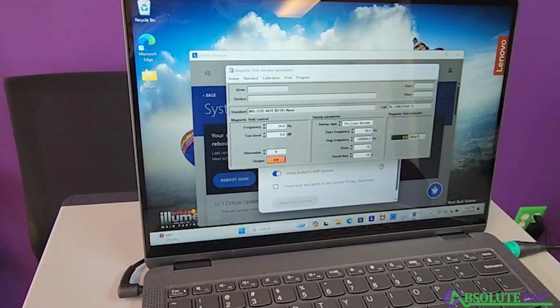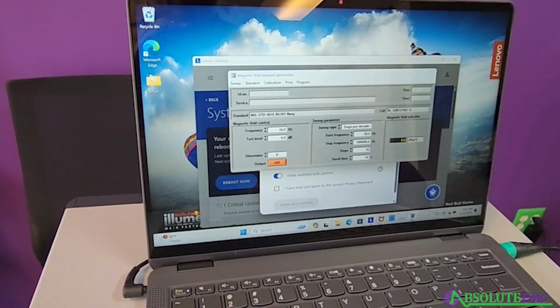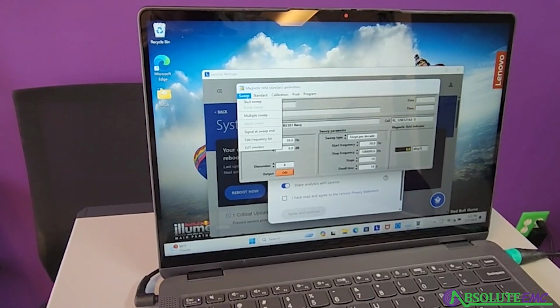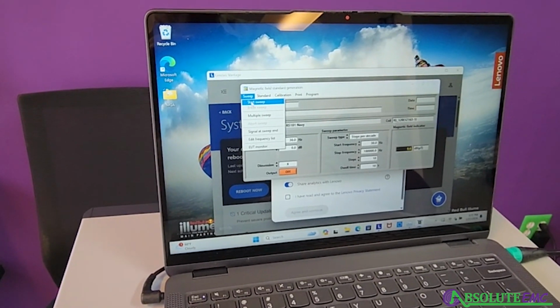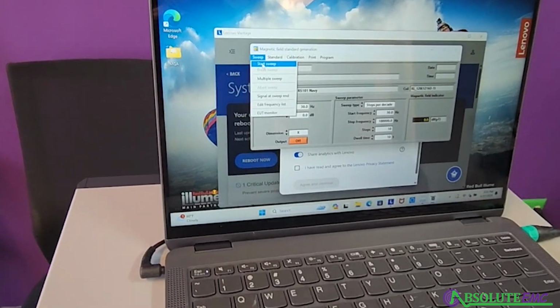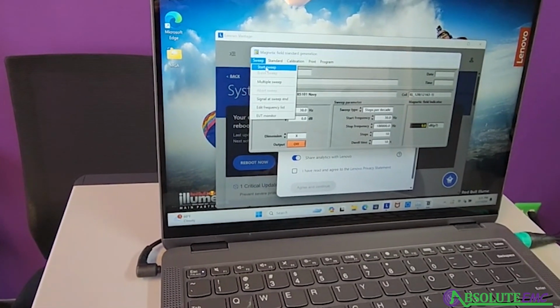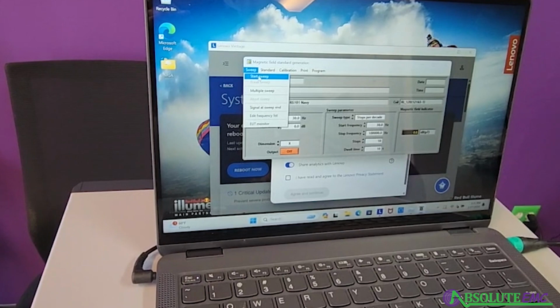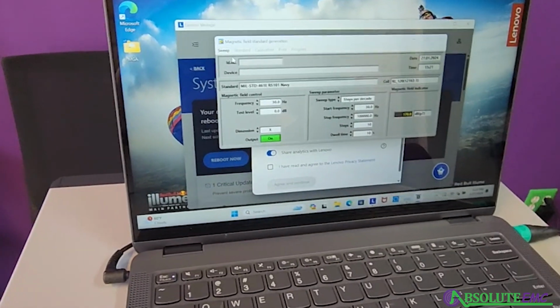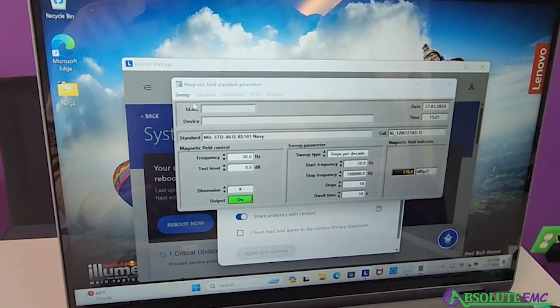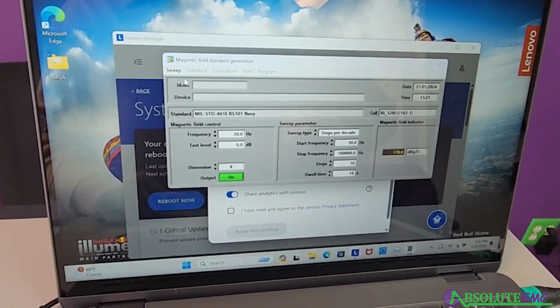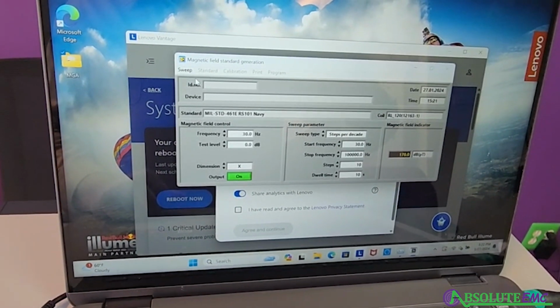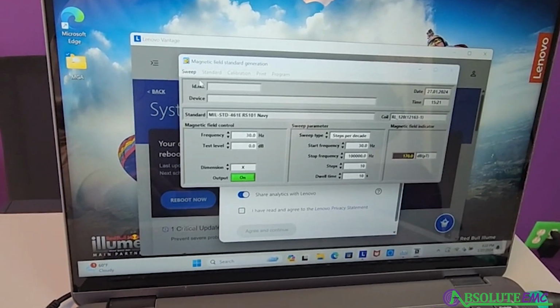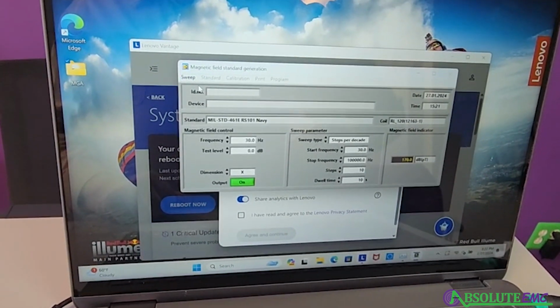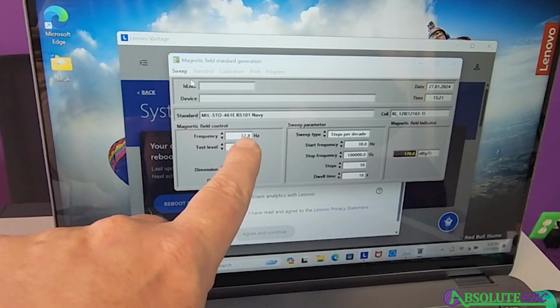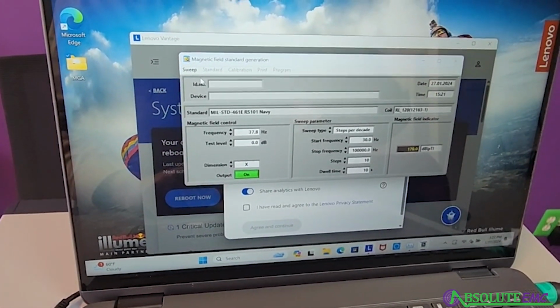This is where we have it, because I did one earlier. And once we have that, we can set up our loop on the DUT that we're testing, or EUT, and hit start sweep. And here it's going to turn it on and get started. And this window is basically just showing what steps we're at.